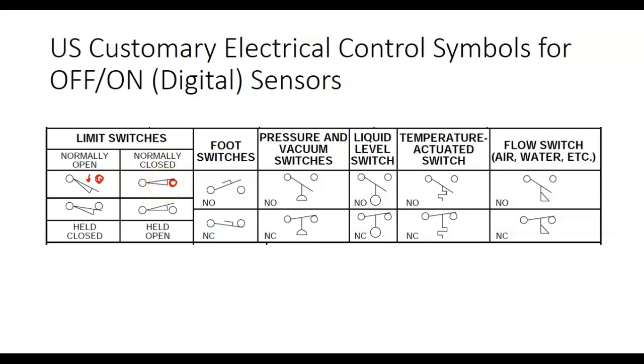The problem with limit switches is that when you park your machine, sometimes it's going to sit on top of a limit switch. So in the normal or parked position of the machine, a normally open might be held closed, or a normally closed might be held open. If you look at this one, gravity's trying to open it, so it must be held closed. On this one, it's not drawn real well, gravity's trying to close it, so it must be held open. So limit switches can fall into that situation.